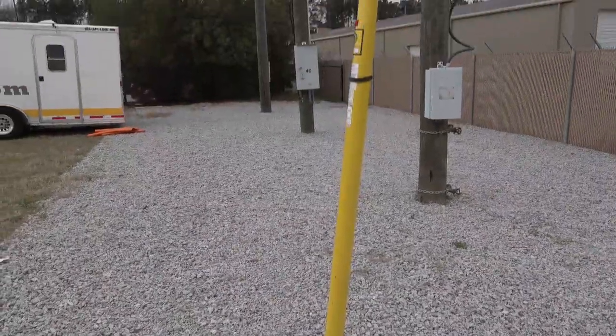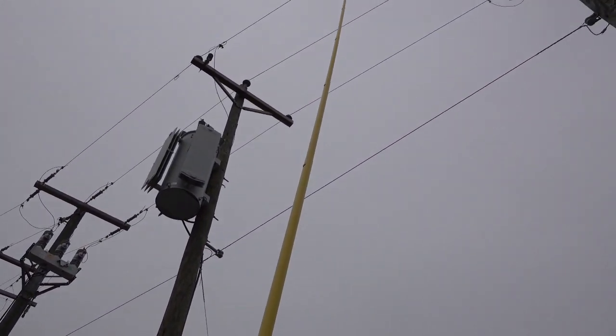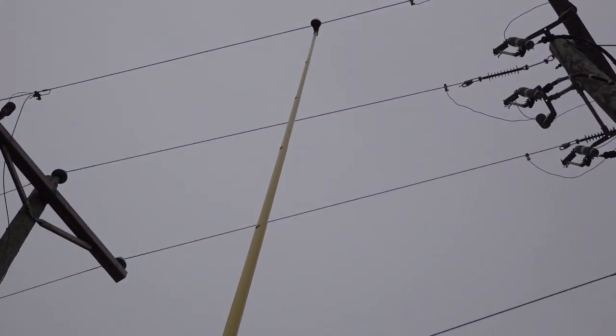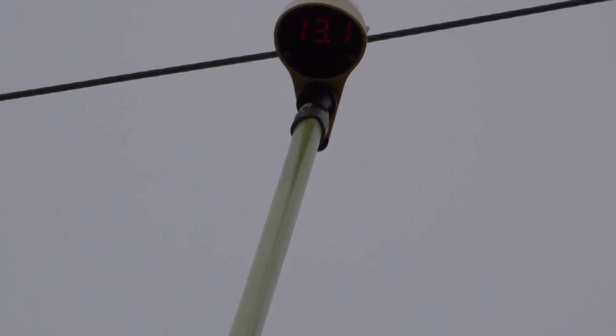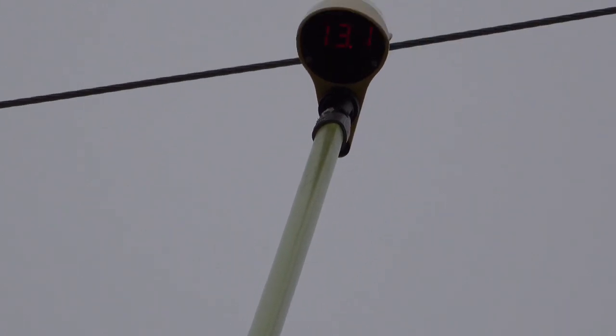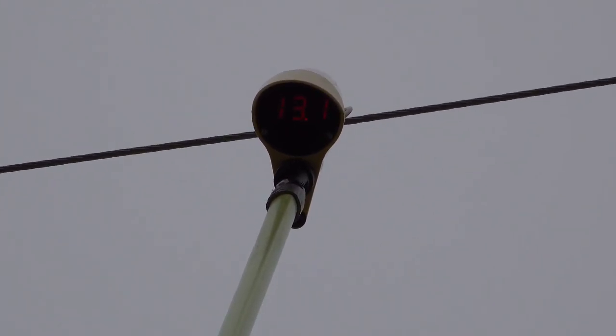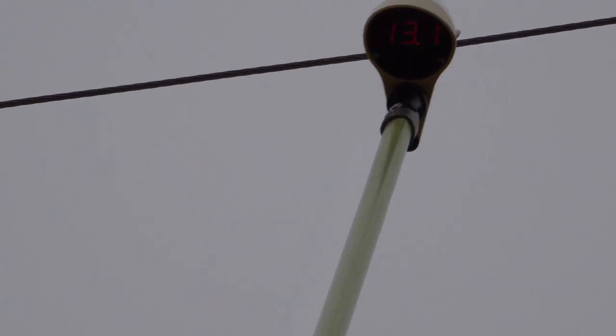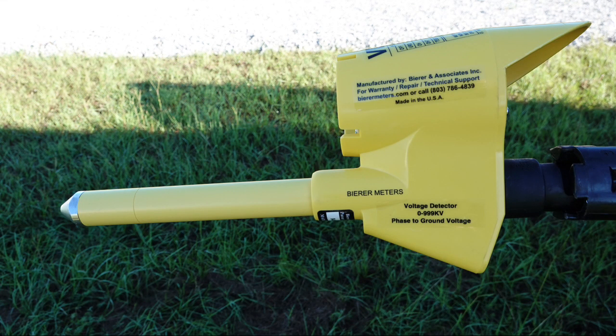Now that we have the VD1000 hanging on the line, let's zoom in and see what the reading is. Notice the VD1000 says 13.1 kV. This is roughly 700 to 800 volts less than what it read on the lower overhead line. The reading is lower because it's further away from Earth and has a harder time to capacitively couple. We do not have any voltage potentials above 40 feet at this location. So in this video, we're unable to demonstrate the VD1000 in the OHT position.